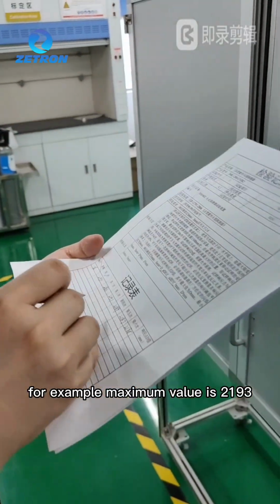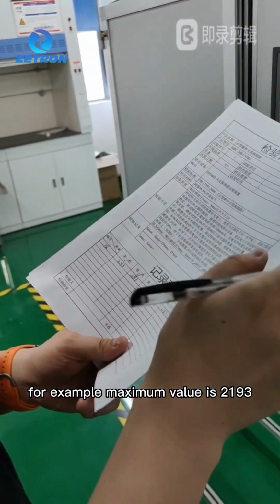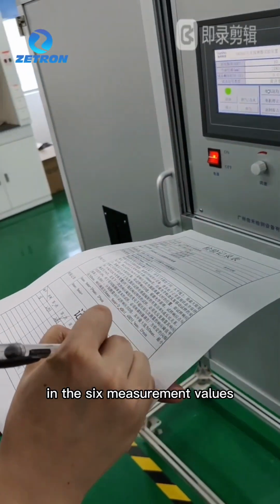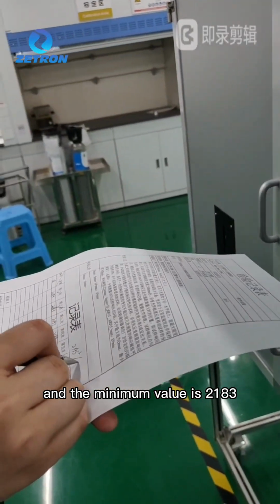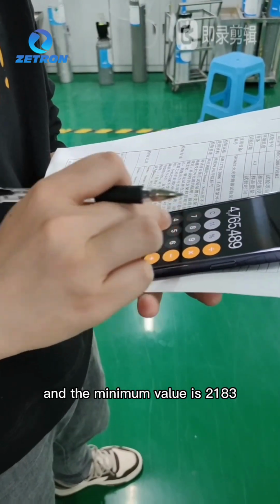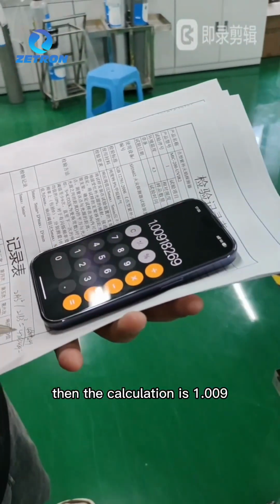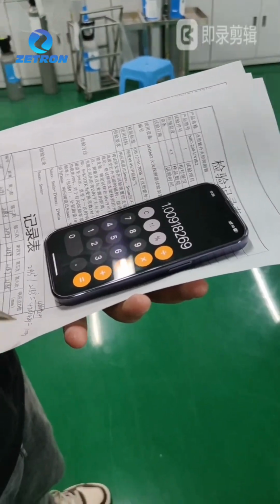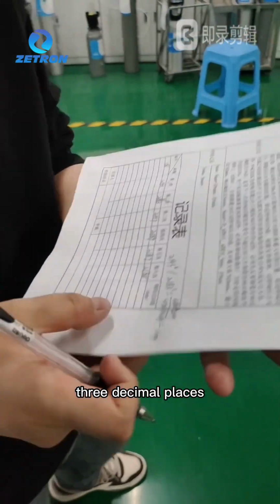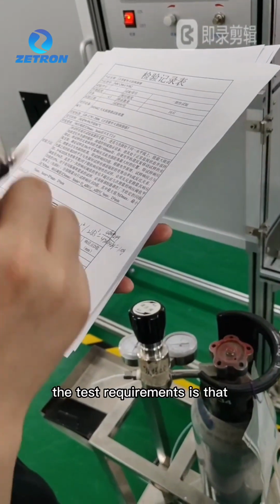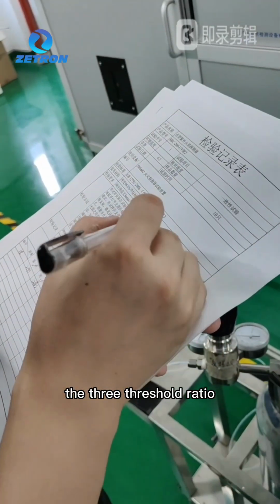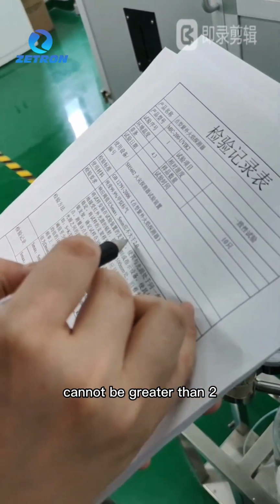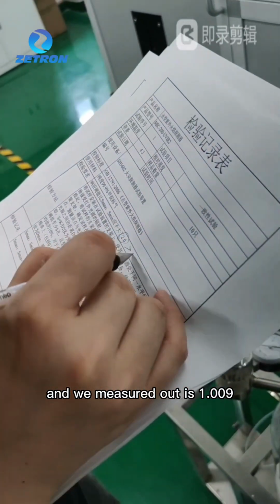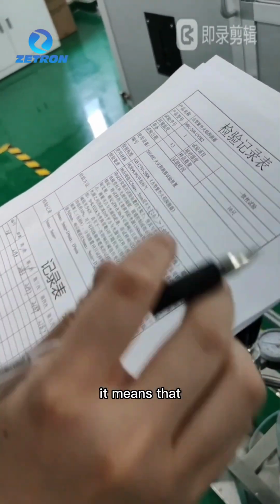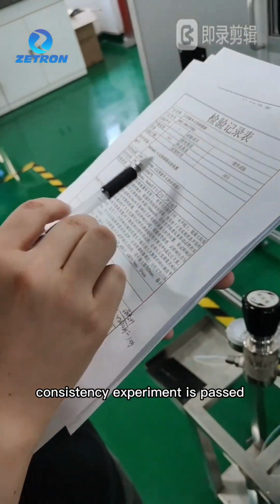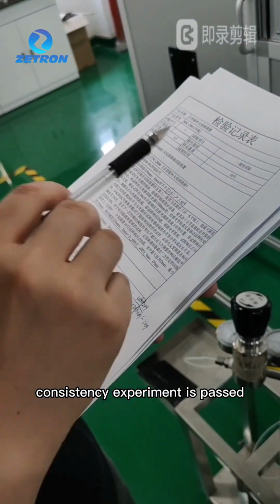For example, the maximum value is 2193 in the 6 measurement values, and the minimum value is 2183. Then the calculation result is 1.009. The result is recorded to 3 decimal places. The test requirement is that the threshold ratio cannot be greater than 2. And what we measured is 1.009. It means that the flame detector's consistency experiment is passed.